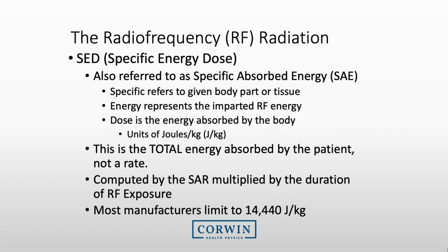Another indicator of RF radiation is the specific energy dose or the specific absorbed energy. Many new systems are using this indicator, which gives the total amount of energy absorbed by the patient. It is simply the specific absorption rate multiplied by the time. Most manufacturers limit this to 14,440 joules per kilogram.